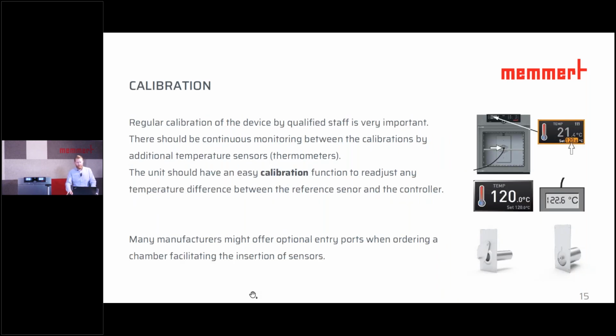Another important factor in ensuring the safe work in the laboratory is the accuracy of the temperature control unit. Regular calibration of the device by qualified staff is very important. There should be continuous monitoring between the calibrations by additional temperature sensors, like, for example, thermometers or external data loggers. How is such a calibration usually carried out?